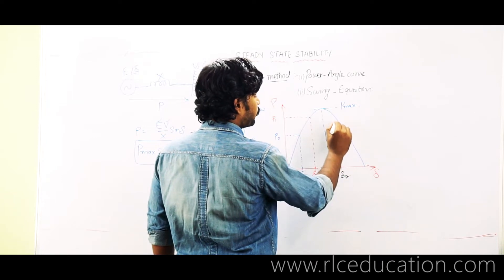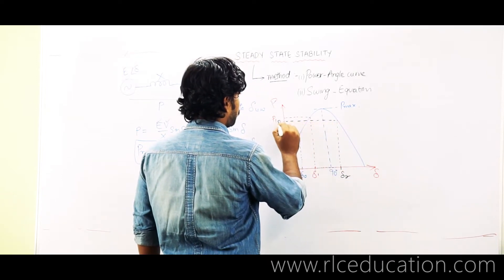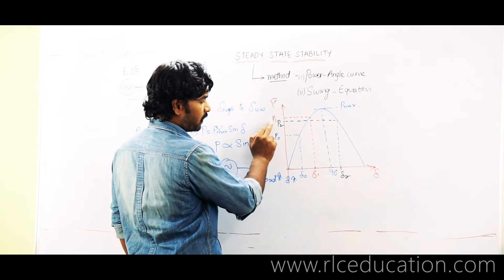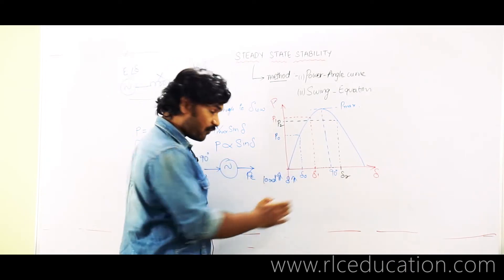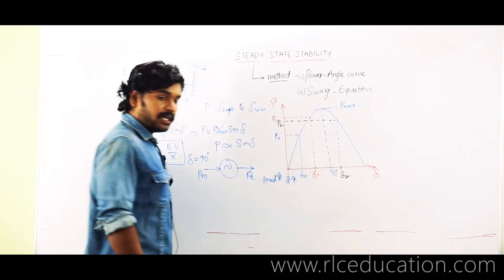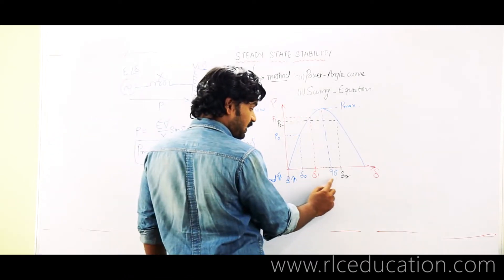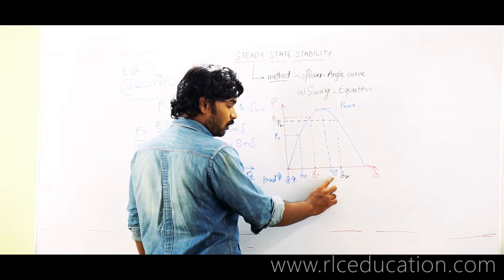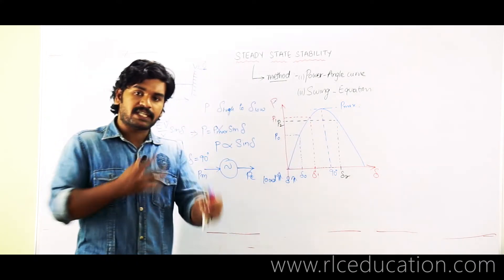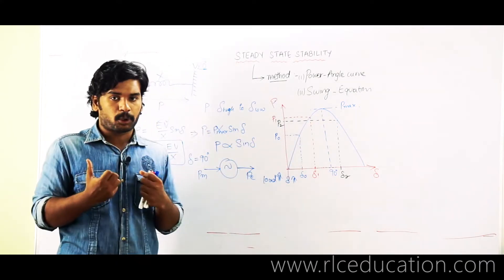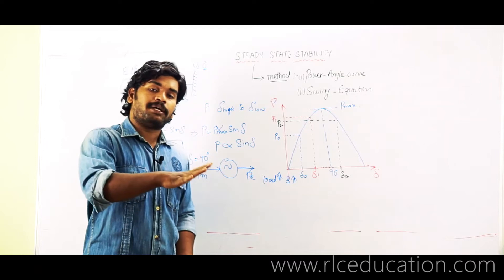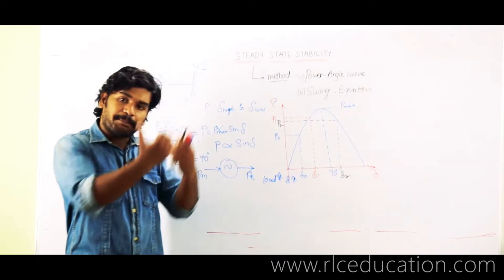The new power output corresponding to delta 2 is somewhere P2. Now you see: when the load was delta 1, the power output was P1. If I further increase the load from delta 1 to delta 2, should the power output increase? But the output has actually decreased — because you have increased the load beyond 90 degrees. If you were increasing the load up to 90 degrees, as the load increased, power output was also increasing. But now the generator is no longer increasing the power output; it is decreasing it.